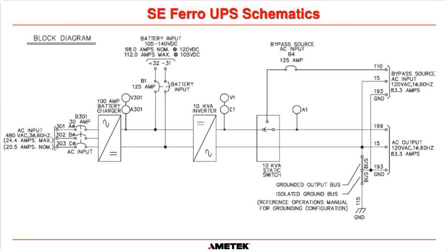And then what I've done is I've blown up the block diagram that's on that first page. And this gives you some really good information that's in a non-schematic form. We don't go into too much detail, but it has all the information that you need. So on the left-hand side here, we have the AC input, and on this system, it's 480 volts in, 3-phase, 60 hertz. And you'll probably notice one thing here. We are not running a neutral to this UPS. And when we get to the schematics, I'll explain that in a little bit more detail.